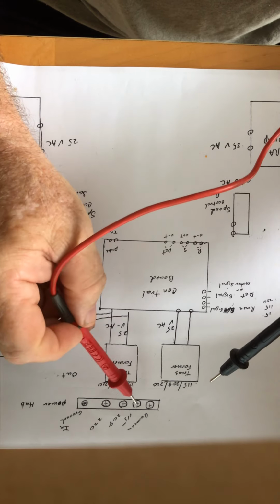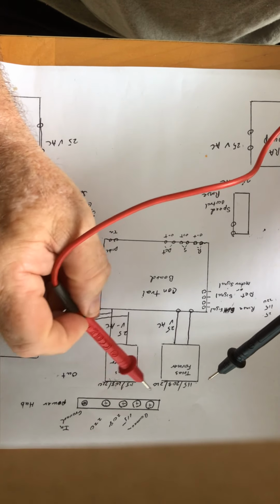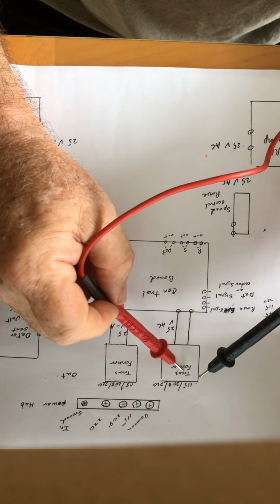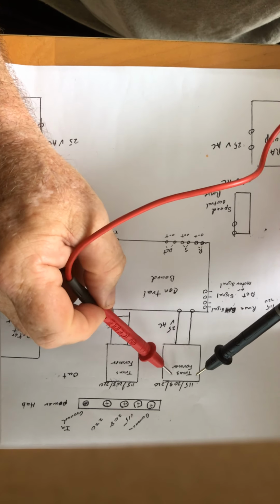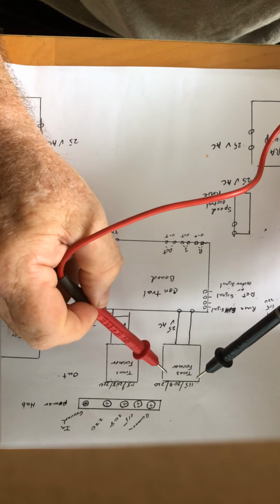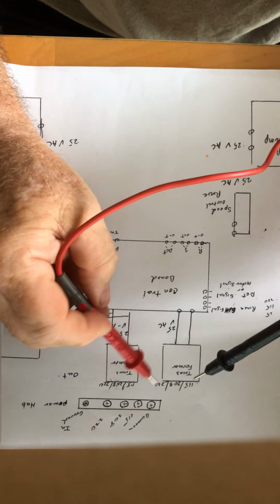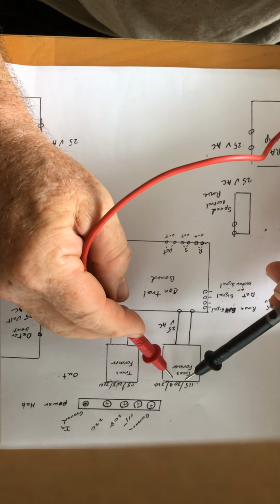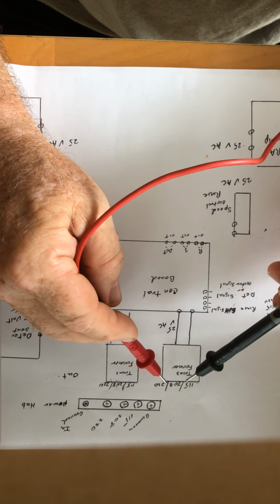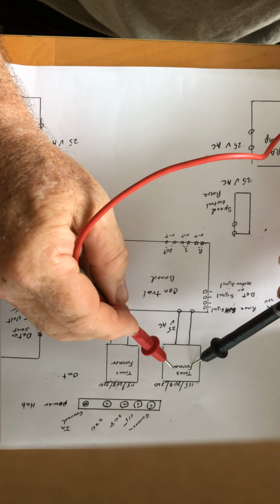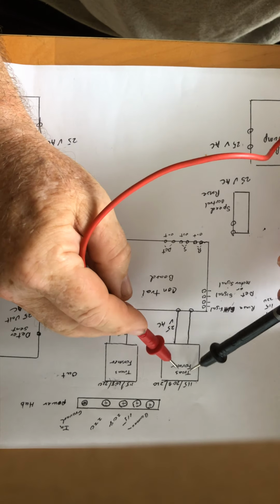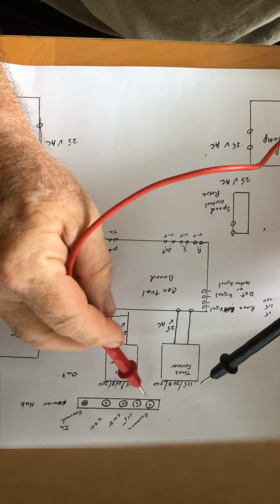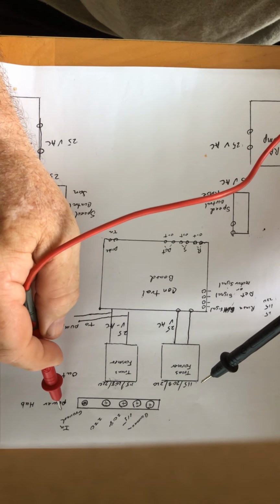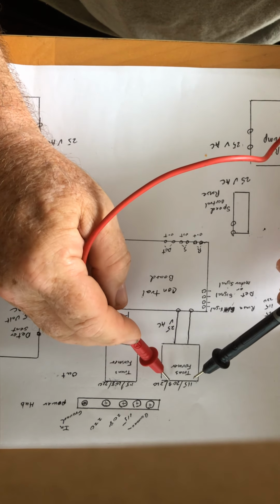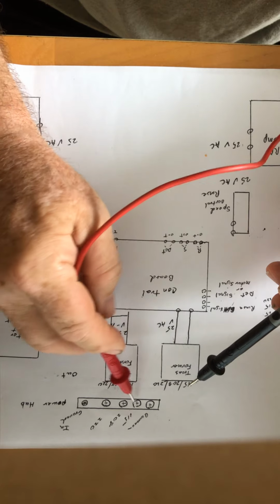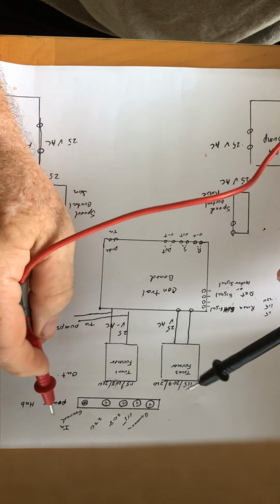And what this does, it takes this power, whether it be 115, 208, or 220, and you can actually look on the transformer and it'll show you what wires you use for 115, 208, 220. For example, maybe the yellow and the white wire would be 115, the red and the blue, maybe 208. You have to look on the transformer itself to see which wires go with what. Basically, if you wanted to, you could take your power line and run it right to the transformer if it's 208 and hook to those wires, but the power hub is a good way to keep things organized.